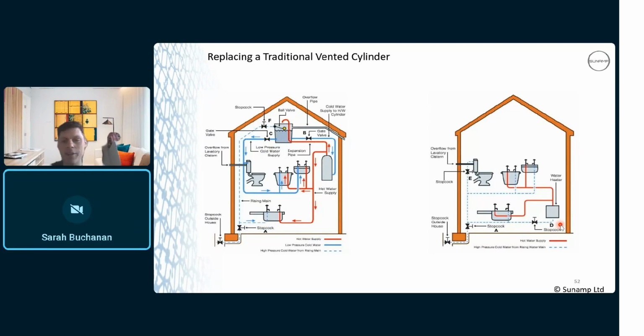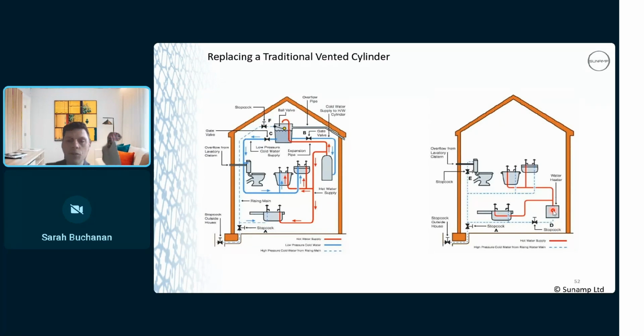Your secondary return, yeah, of course you can do it. How you'd run it - hot water coming out, going around - but where you'd tie that into would be here. You'd have your isolation valve and check valve to stop any backfeed, but you would tie that return pipe into this inlet point here. So that's where you would tie it in.